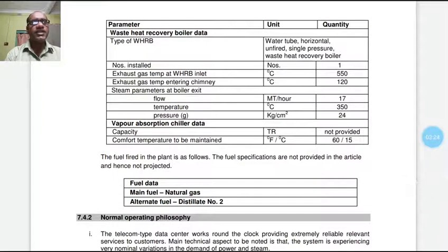Waste heat recovery boiler data: horizontal, unfired, single pressure, installation 1, exhaust gas temperature at inlet 550 degree centigrade and exhaust gas temperature entering the chimney 120 degree centigrade. Steam parameters at boiler exit: 17 metric ton per hour, temperature 350 degree centigrade, pressure 24 bar. For the vapor absorption chiller, capacity is not provided here and the temperature maintained is 60 by 15, that is 15 degree centigrade. The fuel fired in this plant is natural gas and alternative fuel, that is distilled fuel.